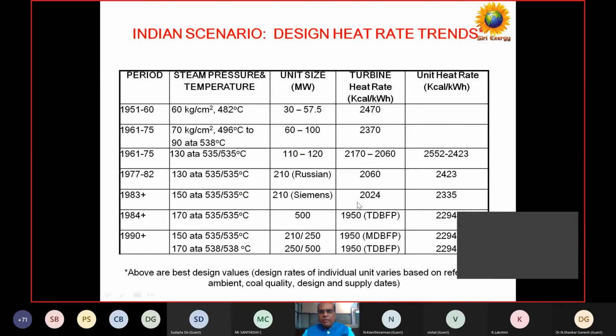I'm giving this example because though we talk about Exergy, in practice we're more familiar with heat rate. Heat rate means: to produce 1 unit of power, what heat energy is required? This has been varying - earlier in the 60s it was around 2500, and now with the latest innovative plants we've reduced it to 2294. That means there's only been an improvement of about 300 kilocalories over this period of 50-60 years.